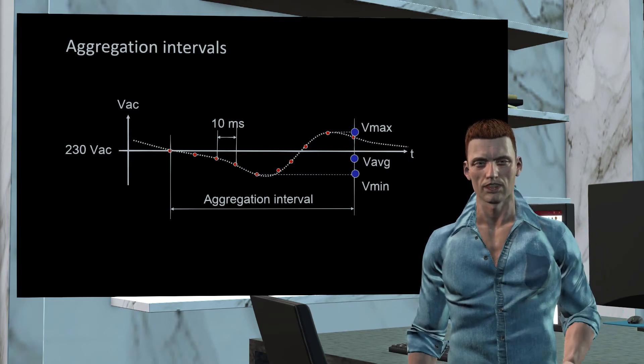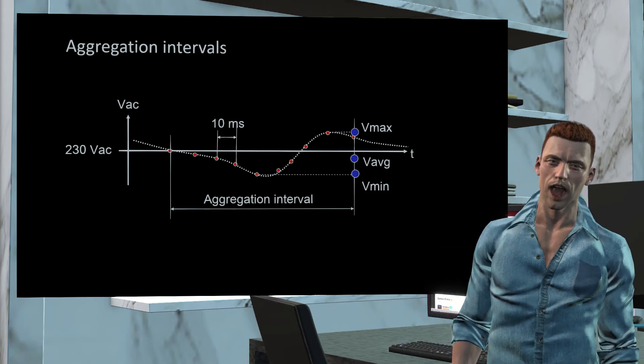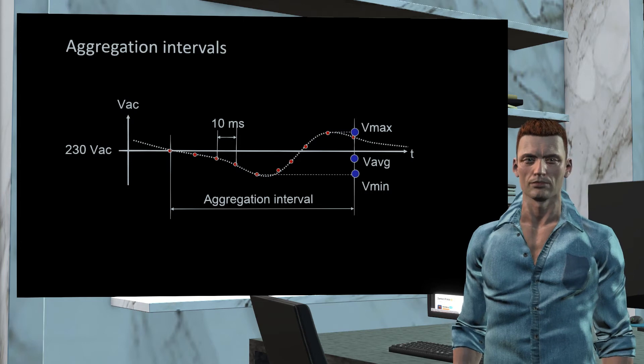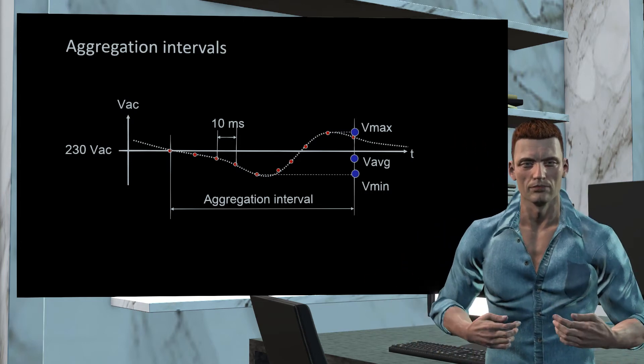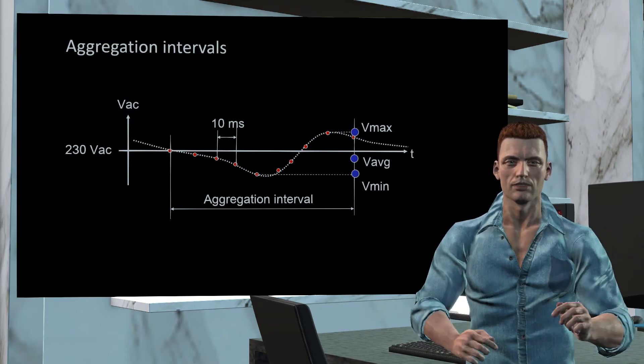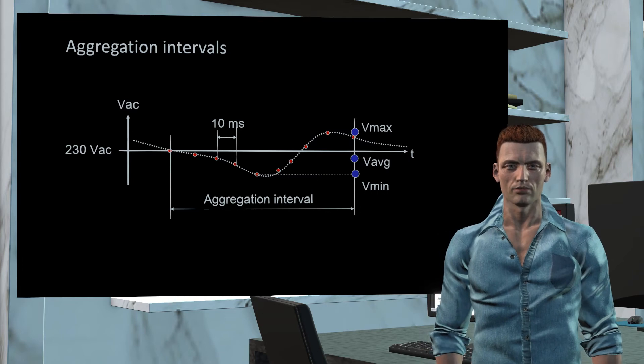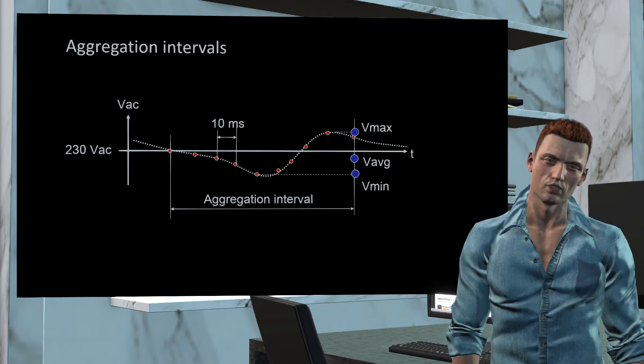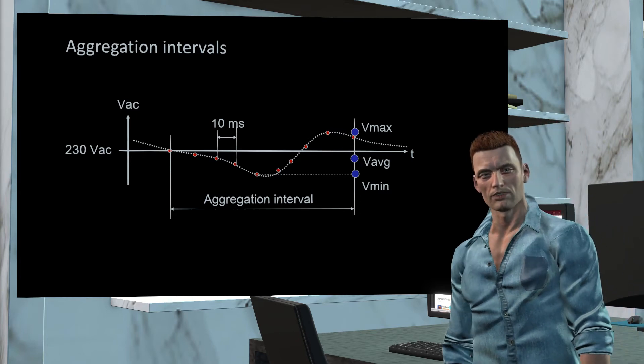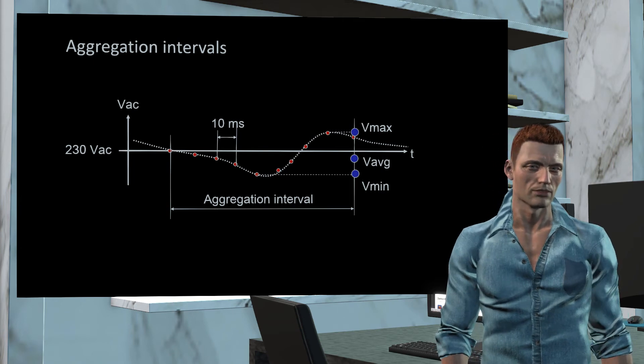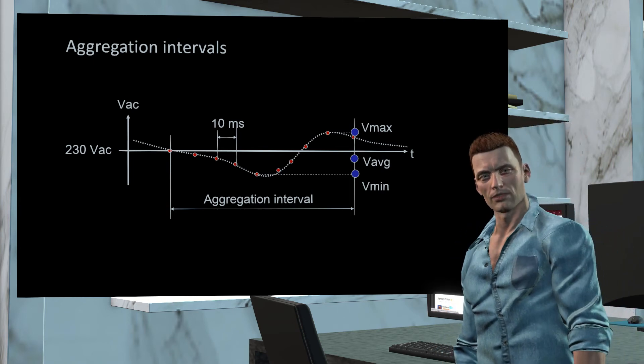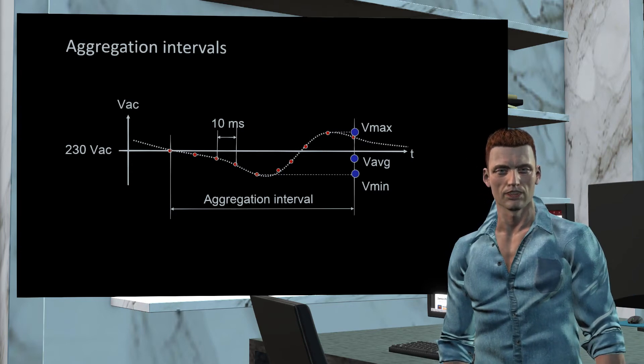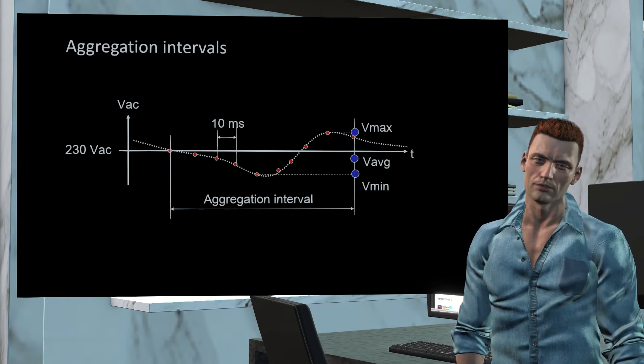These intervals allow compacting the data by means of obtaining the maximum, minimum and average values obtained using those 10 or 12 cycles. In this way, for the aggregation interval of 3 seconds, 15 consecutive measurements of 10 or 12 cycles would be taken and from them we can get the maximum value, the minimum value and the average value of those 15 RMS values. For the 10 minute interval, 10 by 60 by 5 equals 3000 consecutive measurements of 10 or 12 cycles would be taken, and from them we would obtain the maximum, minimum and average value again. Finally, the 2 hour interval is calculated based on the values obtained from 12 intervals of 10 minutes.